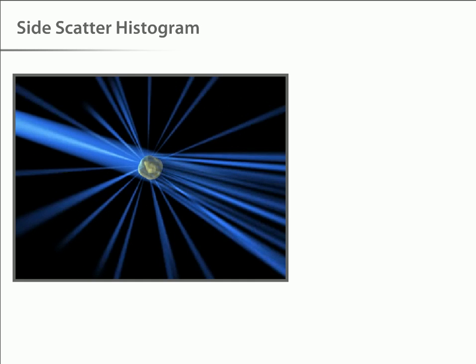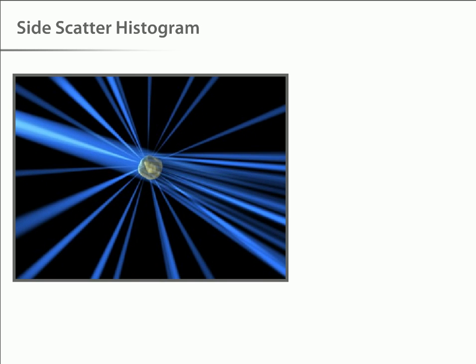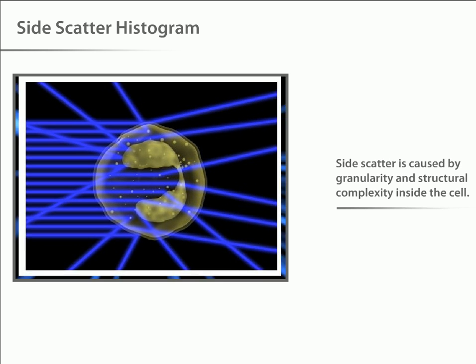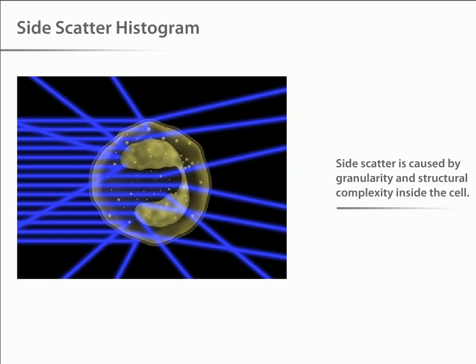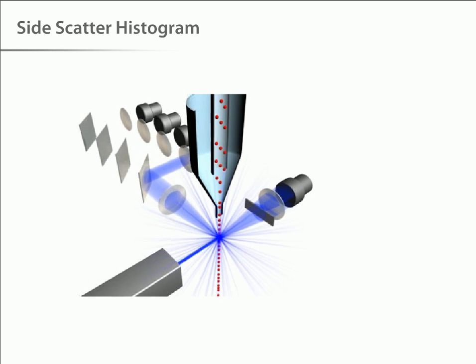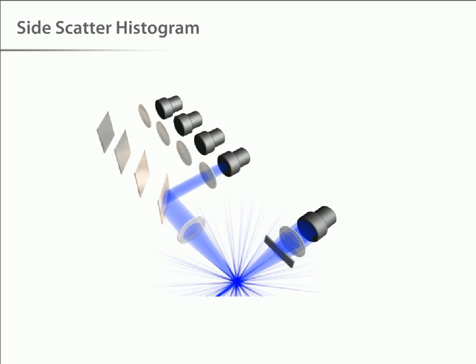As we have already seen, a cell traveling through the laser beam will scatter light at all angles. Light scattering at larger angles, for example to the side, is caused by the granularity and structural complexity inside the cell. This side-scattered light is focused through a lens system, and is collected by a separate detector, usually located 90 degrees from the laser's path.